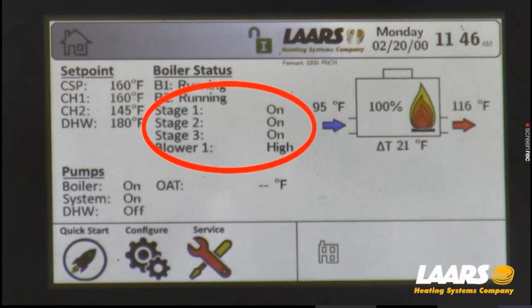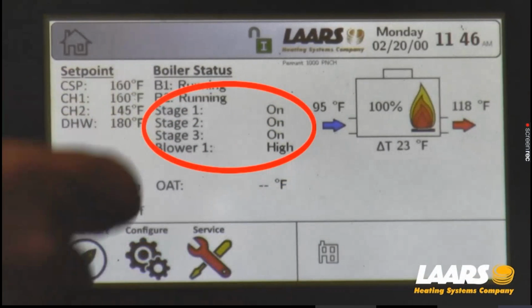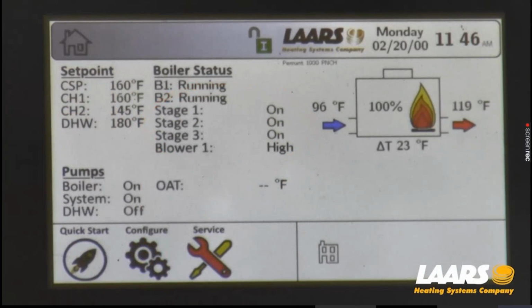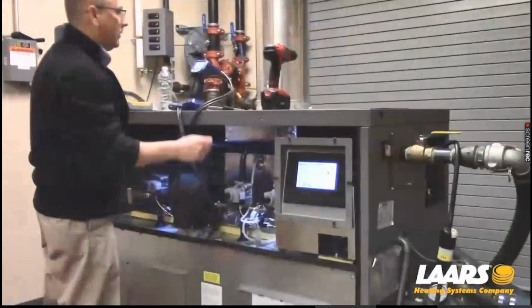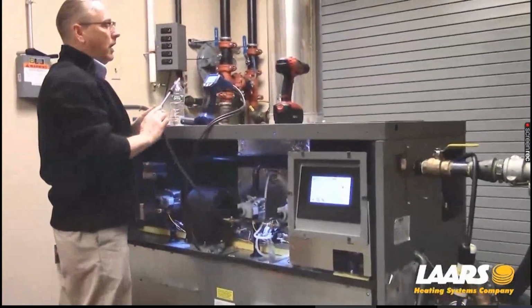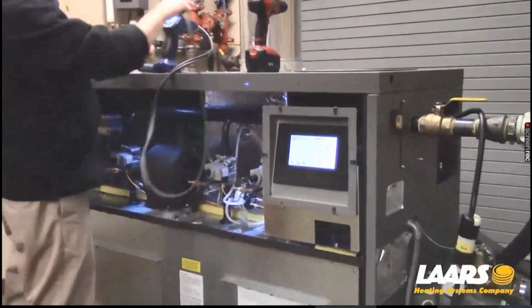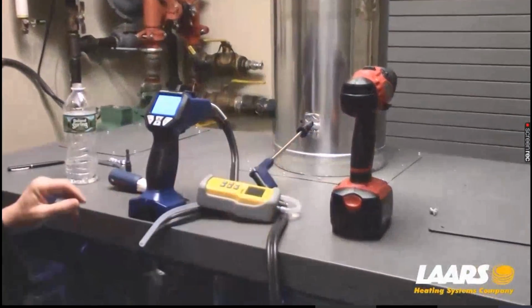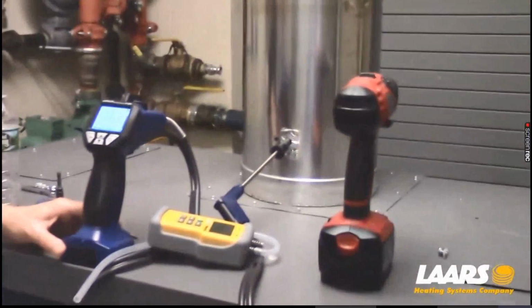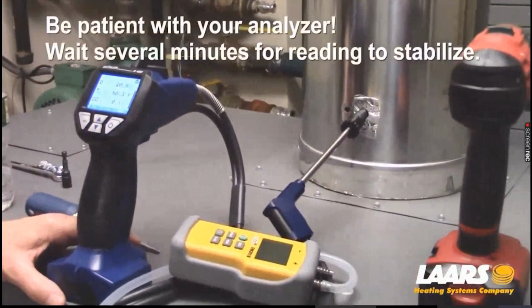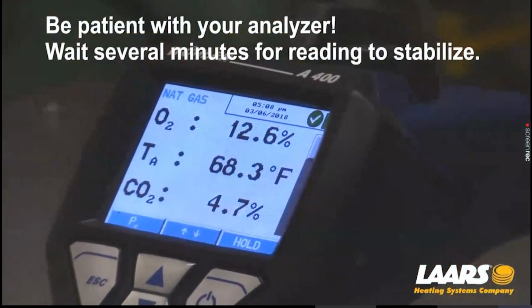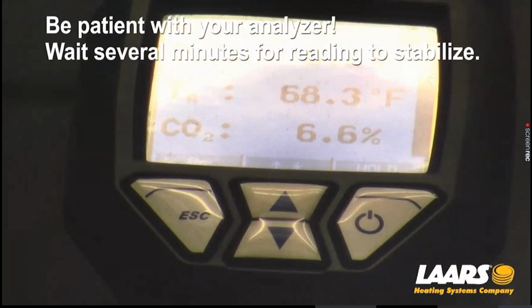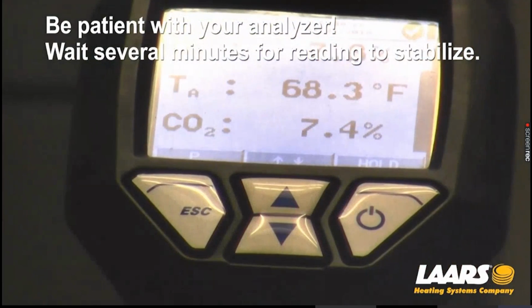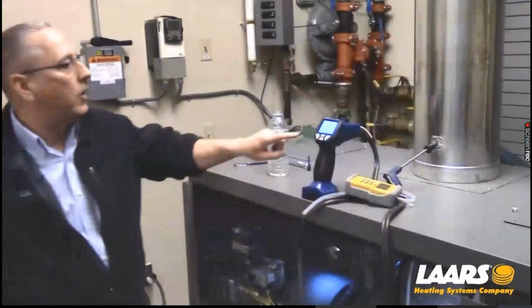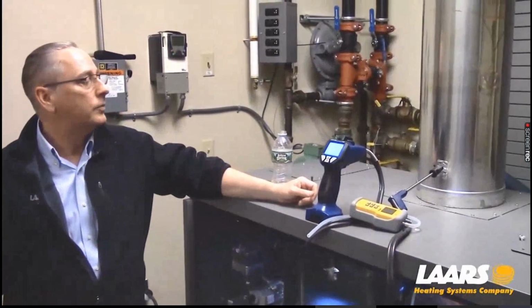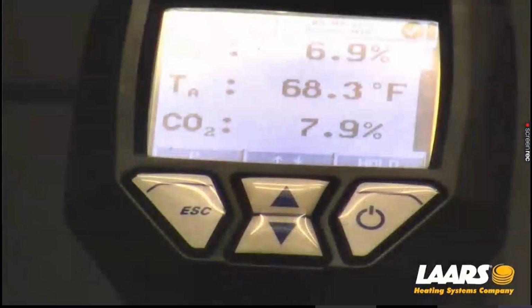Again, this is a 1 million BTU. If we had a 2 million, there'd be 4 stages of 4 valves. We're reading 100%. I can now do my combustion analyzer. I'm going to turn the pump on and install it in the flue. What we're looking for is CO2. So as you can see, we're pretty close to 8% CO2. You can make adjustments, very simple.